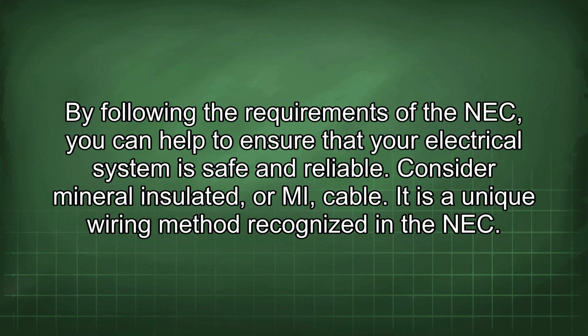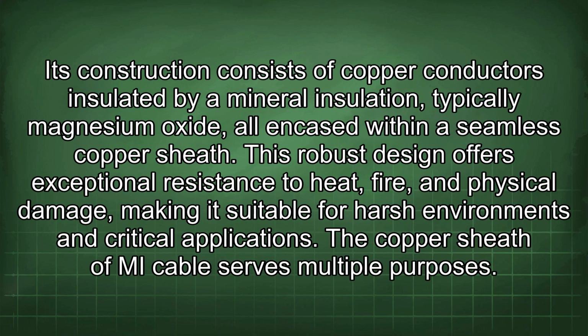Consider mineral insulated, or MI, cable. It is a unique wiring method recognized in the NEC. Its construction consists of copper conductors insulated by a mineral insulation, typically magnesium oxide, all encased within a seamless copper sheath. This robust design offers exceptional resistance to heat, fire, and physical damage, making it suitable for harsh environments and critical applications.